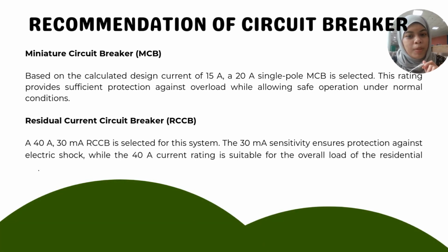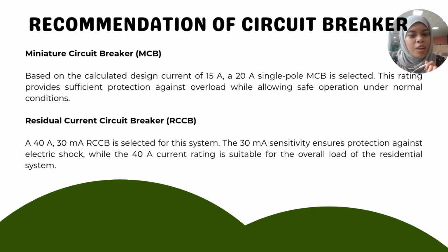So for the recommendation of circuit breakers, the first one is the miniature circuit breaker, MCB. Based on the calculated design current of 15 ampere, a 20 ampere single-pole MCB is selected. The second one is the residual current circuit breaker, RCCB. A 40 ampere, 30 milliampere RCCB is selected for this system. The 30 milliampere sensitivity ensures protection against electric shock, while the 40A current rating is suitable for the overall load.